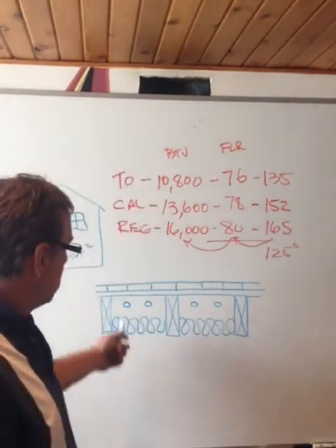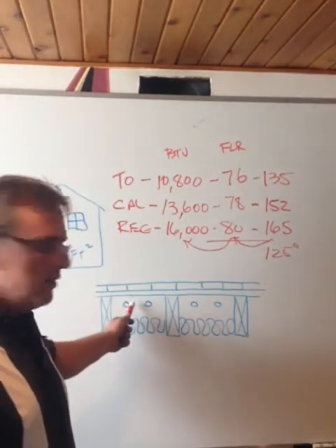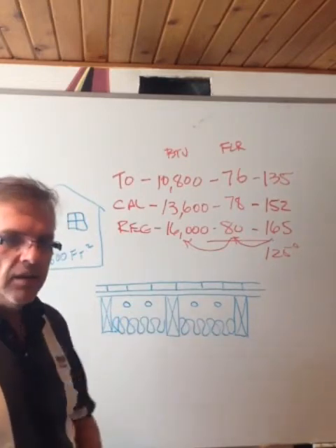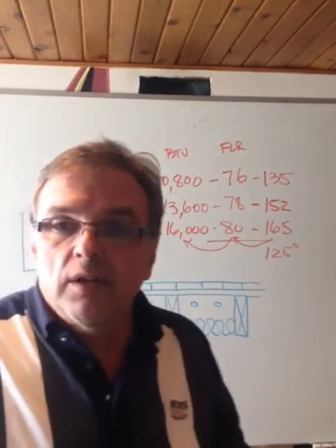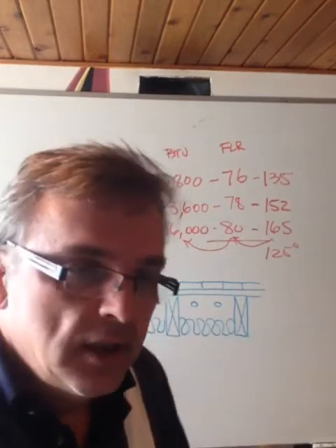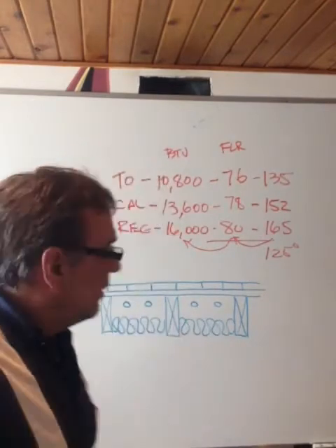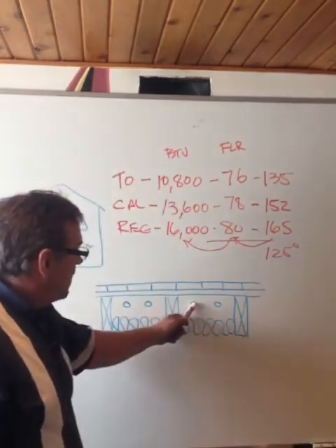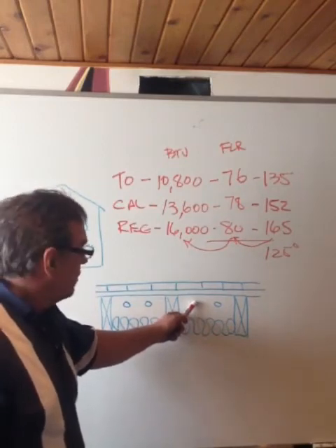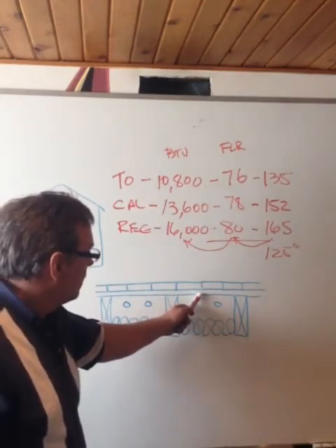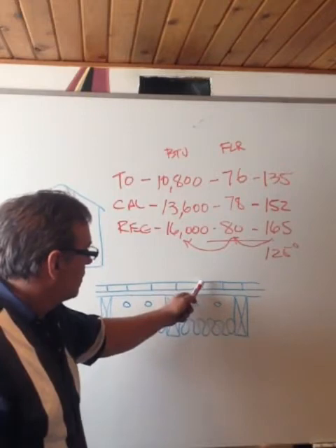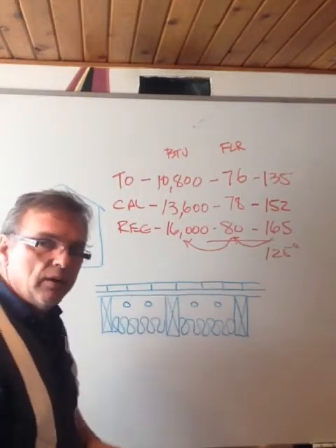And unfortunately, because the tubing is hung in free space, there is no conduction. It's totally irrelevant. All we're left with is radiant. And we have to run very hot water to get the underside of the floor hot enough to meet the resistance of the floor and get the temperature we want here. Right?